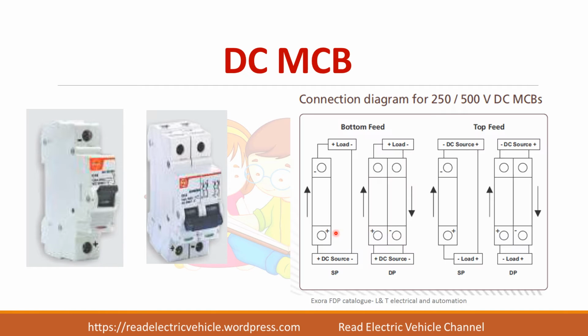So this I have taken from a data sheet from L&T. The connection diagram they have given for these two MCBs. So you see here single pole 1. So in single pole we have seen plus at the bottom. So they have taken this plus here. Connect to the plus of the battery or DC source. Let us take it as a battery. So the plus of the battery will be connected to the plus of the MCB. And minus of this MCB should be connected to the positive terminal of the load, and the negative terminal of the source is connected to the negative terminal of the load. So for these two MCBs they have given the connection.